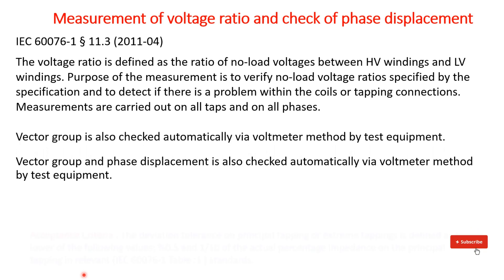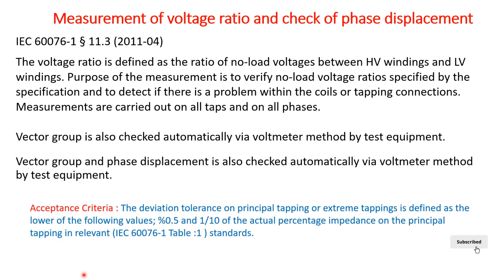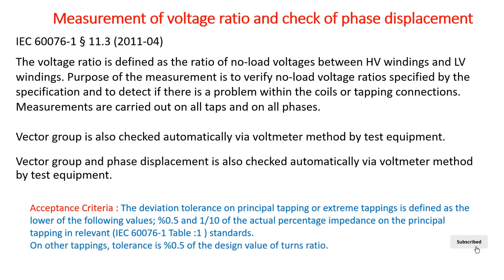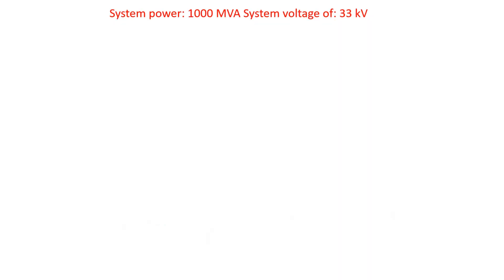The acceptance criteria — the deviation tolerance for the principal tapping and extreme tapping — is defined as the lower of the following values: 0.5 percent, and 1 over 10 of the actual percentage impedance of the principal tapping, as per IEC 60076-1 Table 1. For other tappings, the tolerance is 0.5 percent of the design value of the turn ratio.